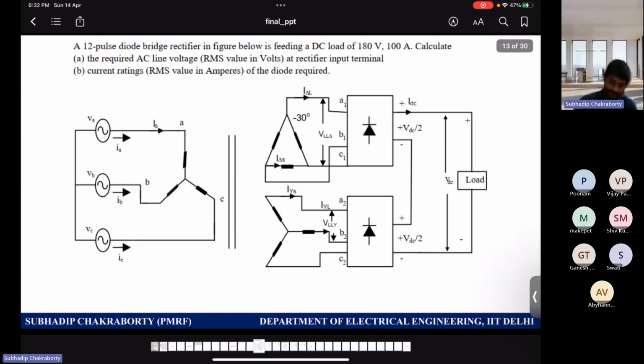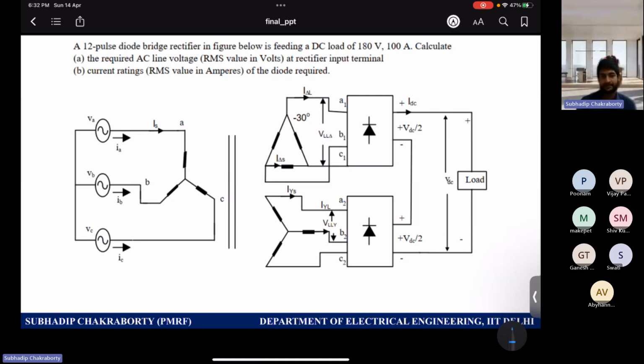So why is the transformer used? You must have seen this diagram quite a few times. Now I think you are clear why these transformers are used. Star-delta transformers are there to provide different phase shifts, because if you use star-star, no phase shift occurs, since star-star is a phase-to-phase transformation, and phase-to-phase transformation gives no phase shift. To provide phase shift, since phase-to-phase transformation happens, the line voltage is 30 degrees phase shifted by star and delta. So to achieve the phase shift, a star-delta configuration connected with another transformation is useful, so the currents can be phase shifted and then added back, benefiting the current quality.